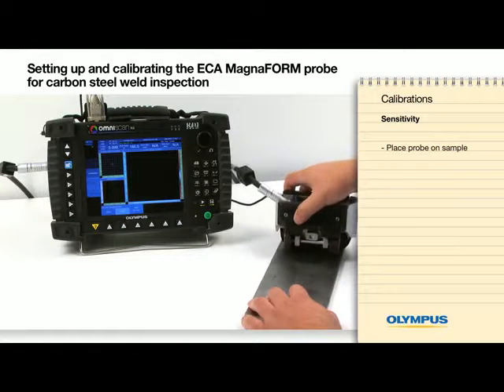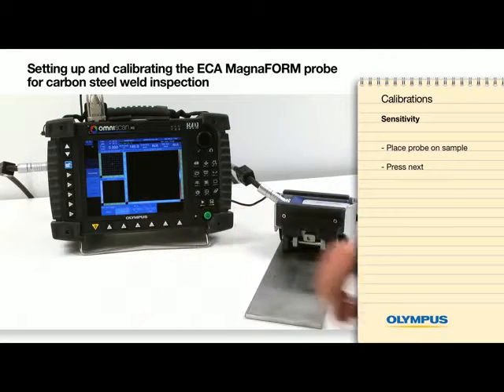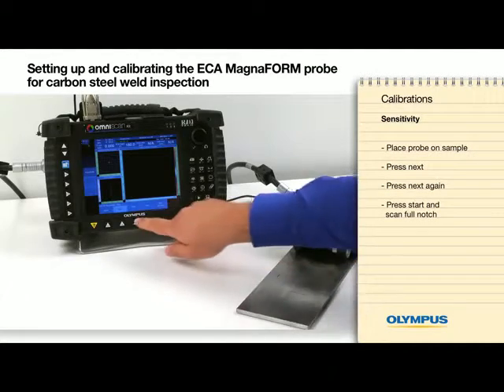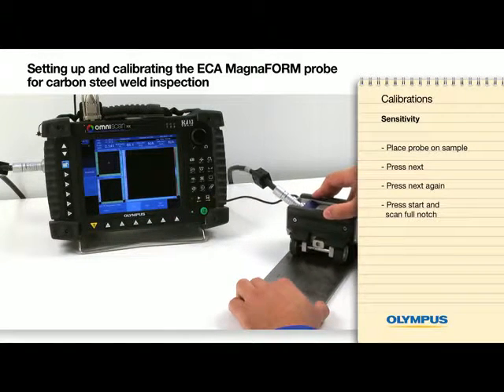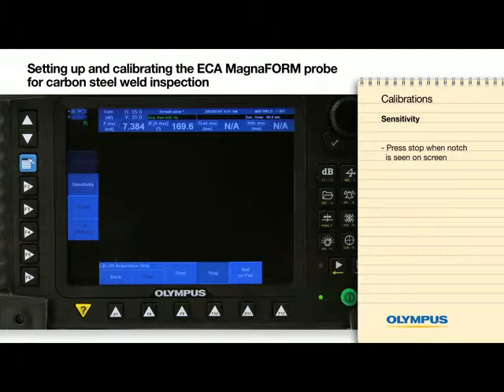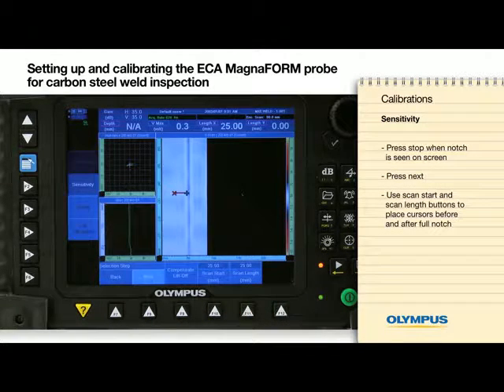Place the probe on the carbon steel calibration sample and press Next. The default settings are correct for this type of material — press Next again. Press Start and scan the full notch. Press Stop once the notch is seen on screen, then press Next. Using the Scan Start and Scan Length buttons, place the cursors before and after the full notch.